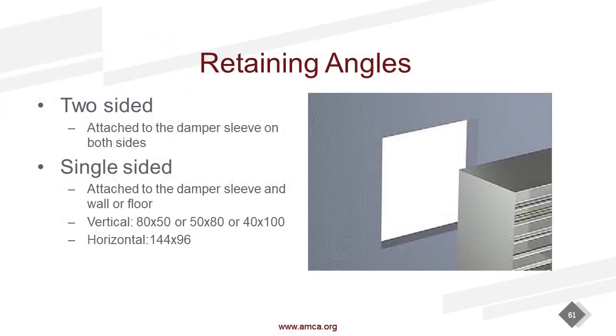The theory of floating in that expansion clearance when I'm expanding under heat is the same for the retaining angle. If I fasten the angle to the wall, I now have a rigid installation. That damper will not be able to move. It's not approved to have the fastener on the wall on a 2-sided angle. So again, the fastener only goes through the damper sleeve. These are very easy things to miss in inspection. There's a checklist of things I've created.